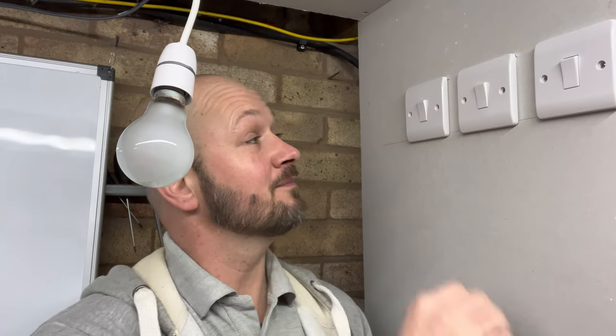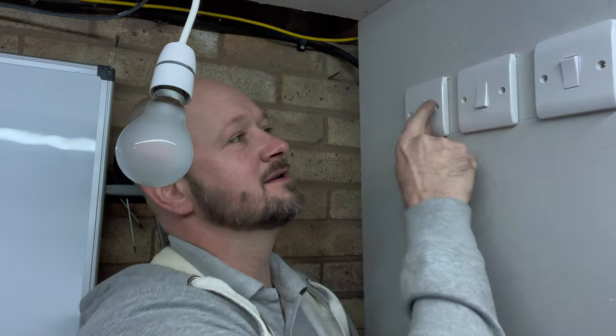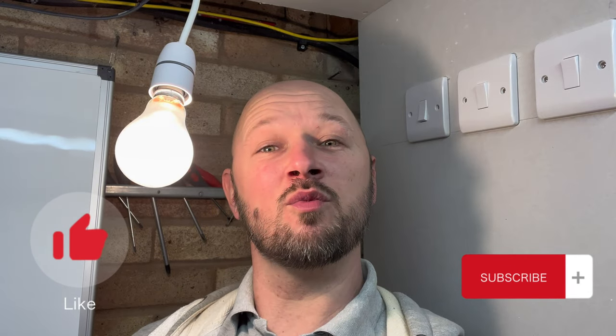So there you go — that's how to wire a lighting circuit with two two-way switches and an intermediate switch. Let's see if it works: you get to the bottom of the stairs and want the light on — it works. You get to the midway and want to turn it off — you can. At the top floor you want it back on for the way downstairs — you can turn it on again. Whichever way you switch these lights, it does exactly what you want. If you like this type of content, leave a like, subscribe, and comment below to let me know what wiring diagrams or sequences you'd like to see next.